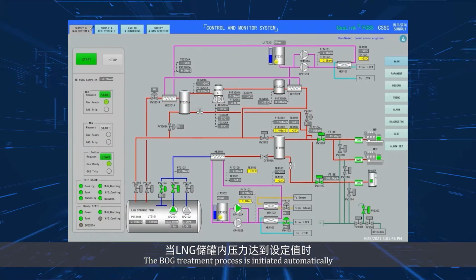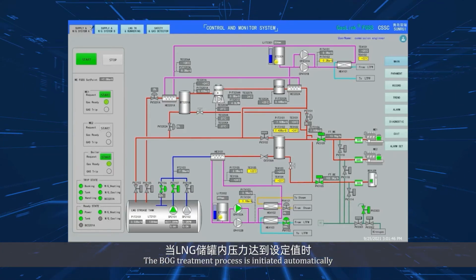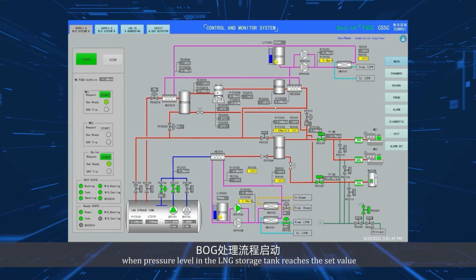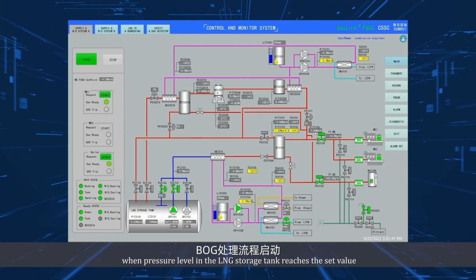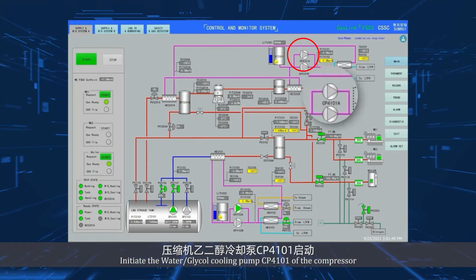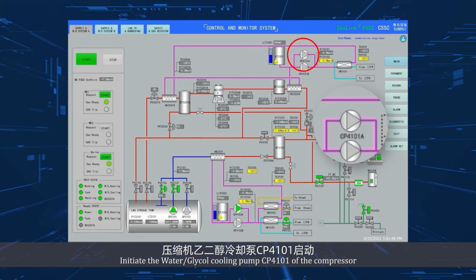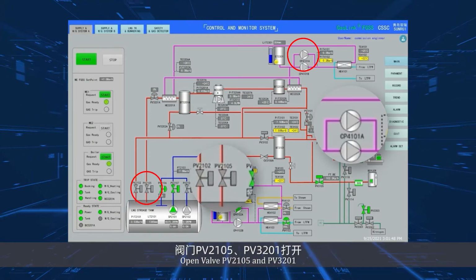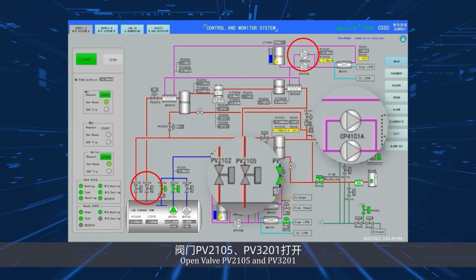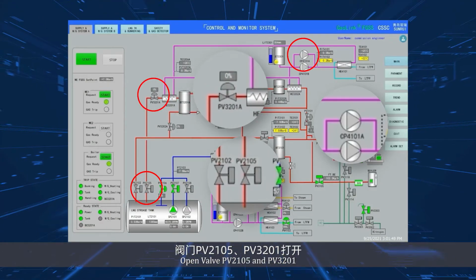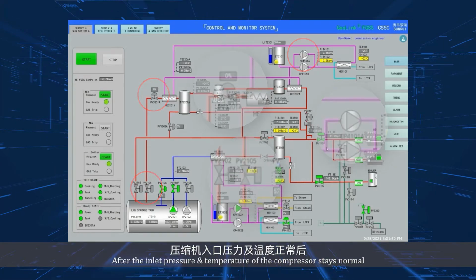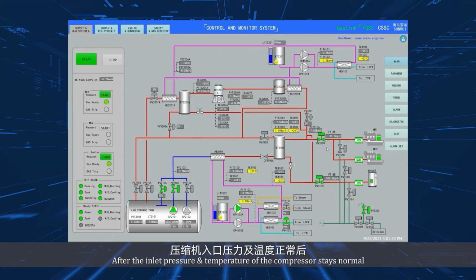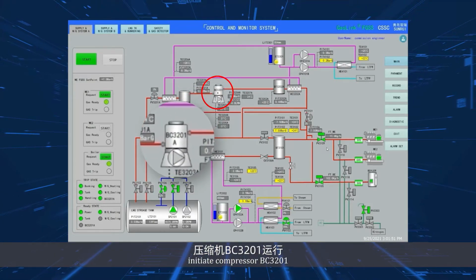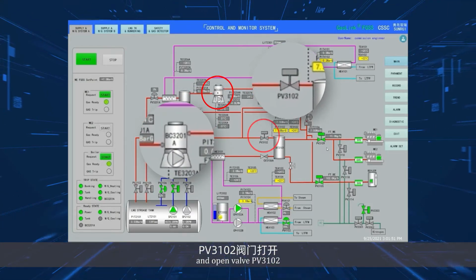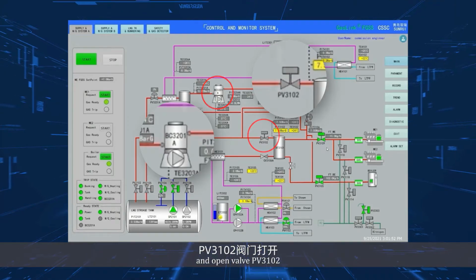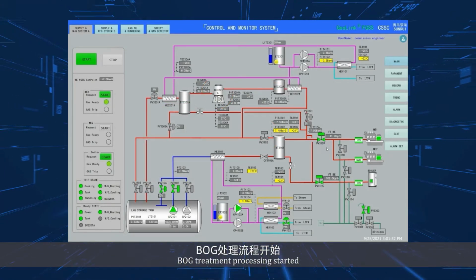The BOG treatment process is initiated automatically when the pressure level in the LNG storage tank reaches the set value. Initiate the water-glycol cooling pump CP4101 of the compressor. Open valve PV2105 and PV3201. After the inlet pressure and temperature of the compressor stay normal, initiate compressor BC3201 and open valve PV3102. BOG treatment processing started.